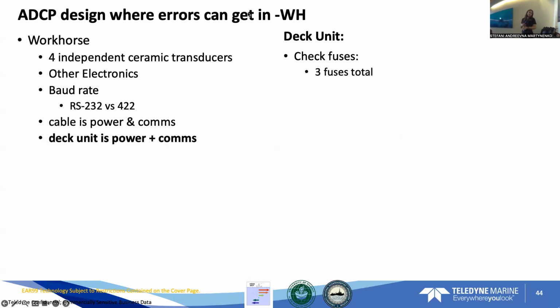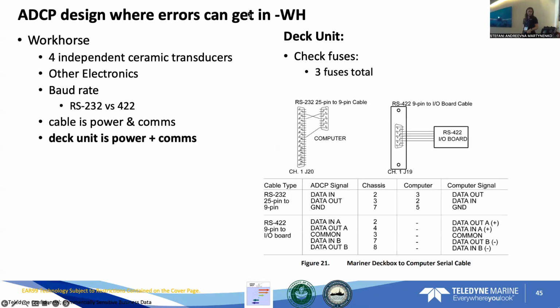So for the deck unit, if there are any issues with it, the first pass is to check fuses. There are 3 fuses. Again, the manual goes through the details of where those are all laid out, but the first check is the fuses and then the pinout again, just checking that you're getting your comms and your power through that.